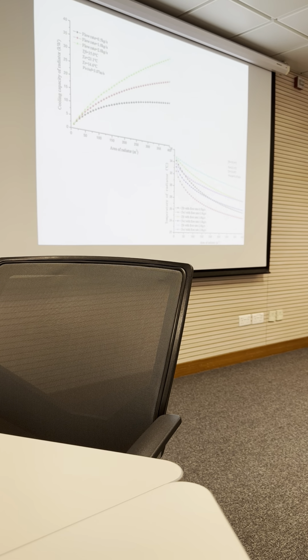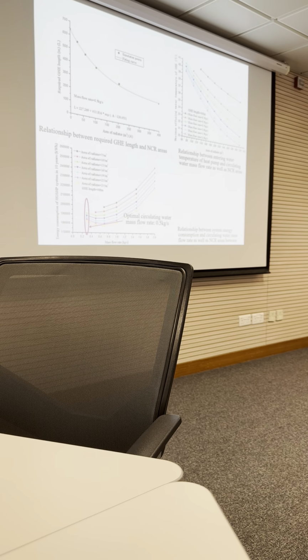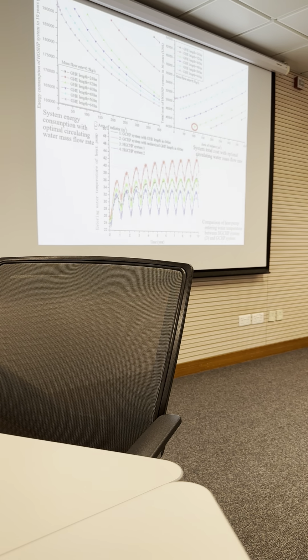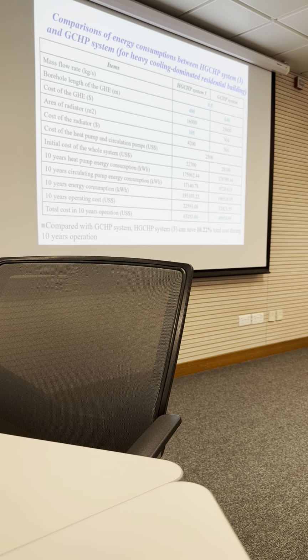And you can see the research found that the COP could be much higher. This cooling capacity of radiator depends on the flow rate and temperature, of course. The total energy, total cost, you see, it depends on depth of the borehole as well. I think we need to compare this one. The hybrid system compared with the ground coupled heat pump system without the previous three methods, then you can see the total cost is much less. I save 10.22% of the total cost over 10 years.